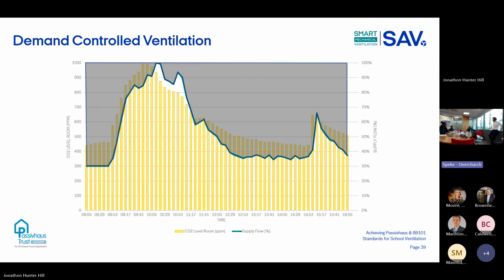So you'll have that as well. More so, like you were saying, if the demand in one room is lower, you think the air gets redistributed to other rooms. But it seems not balanced then. Otherwise, the main fan that is providing the motive force will modulate as well to respond to the lower demand rather than redistributing it. You know, if you have a fixed, cheap system, they're looking at their budget and they don't want to balance, they just want every room to have the same volume going through. That is not going to work.